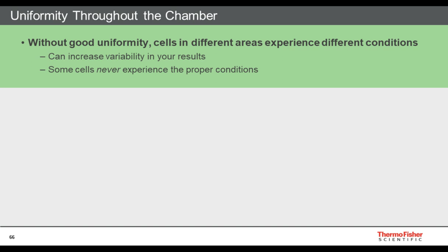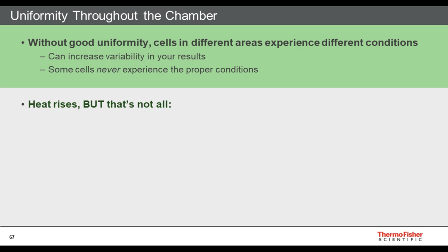If I look at this a little bit closer, if you think just about temperature, hot air rises, right? If you stay in one of those fancy hotels with a big atrium that's maybe 14 stories high, and you get off the elevator on the 14th floor, and the whole space is open all the way down to the ground floor, you find that the temperature is much warmer on the 14th floor than it is on the first floor. So we know that heat rises. But that's not all. It turns out that carbon dioxide gas is heavier than air, so it sinks. And nitrogen gas, used in a hypoxic incubator to decrease the oxygen concentration, is lighter than air, so it rises.